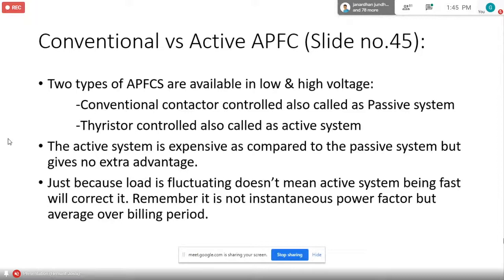Remember, it is not instantaneous power factor, but the average over the billing period. So you've got a half-hour billing period, and you have to correct that. Not in seconds. They will say, oh, this will correct it in seconds. So you don't need that.